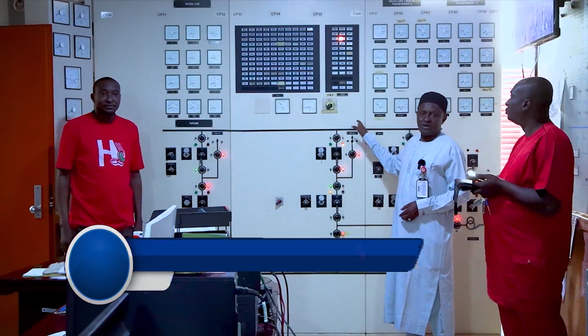This is the 132 kV panel, and here we can see we have 3 outgoing lines on 132: the 132 kV Shiroro-Minna line 1, 132 kV Shiroro-Minna line 2, and the 132 kV Tegina line. Then we have 2 transformers, that is the 2 by 150 MVA transformers, stepping down from 330 to 132 to 33. So the 2 transformers provide the 132 kV to bus bar 1 and bus bar 2. From here, we now evacuate the energy to Minna and also to Tegina.